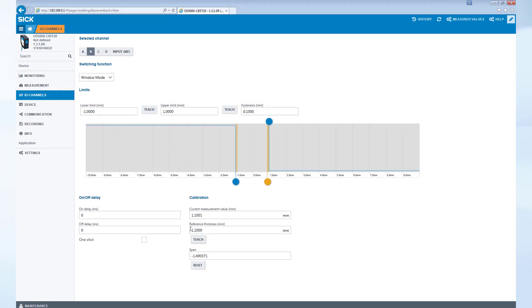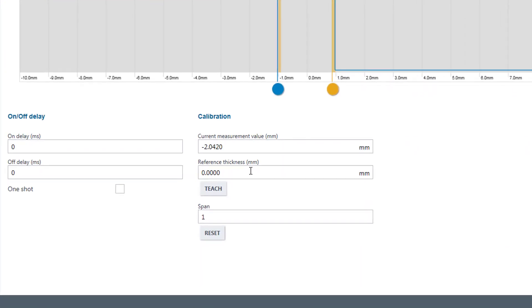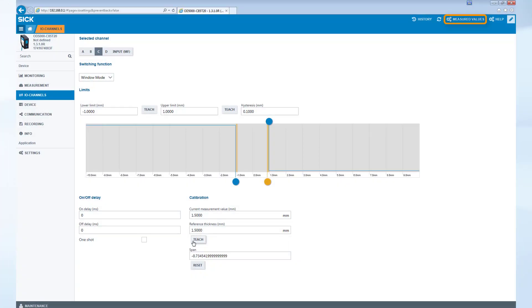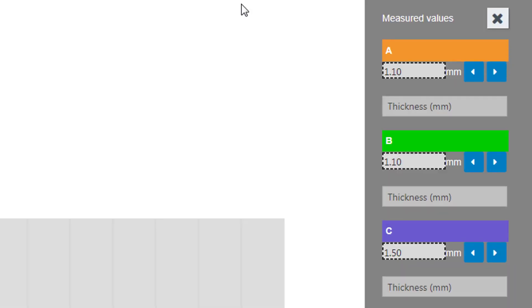Finally, channel C is used for the gap between the two glass targets. Type the reference value into the input field, 1.5 mm in our case, and select Teach. Select measurement values on the top right corner to access the values.